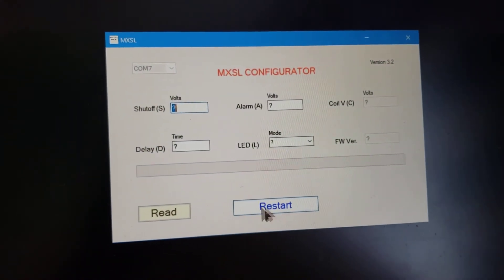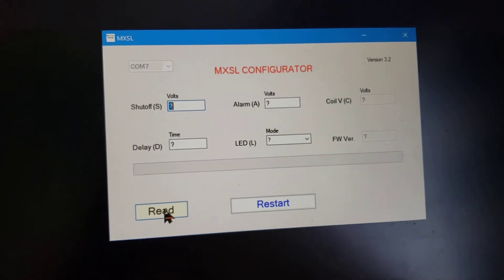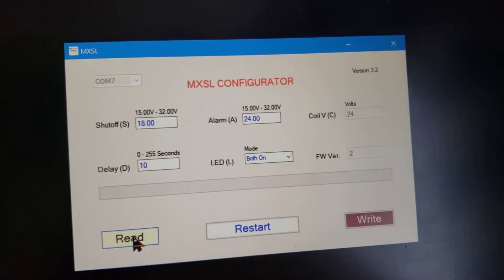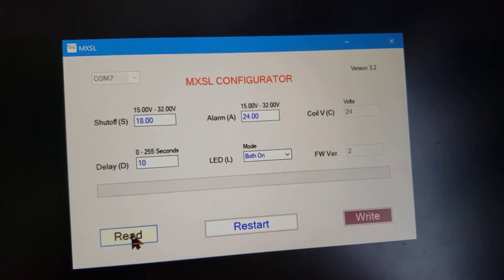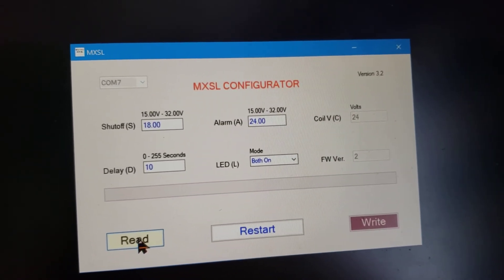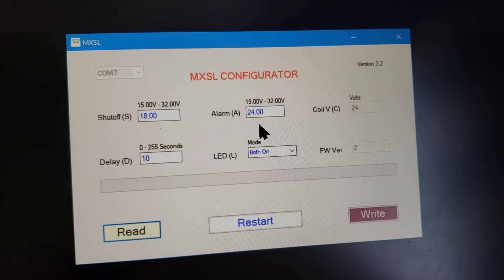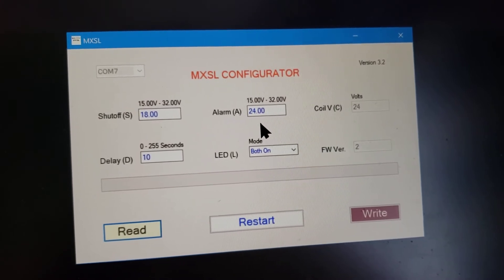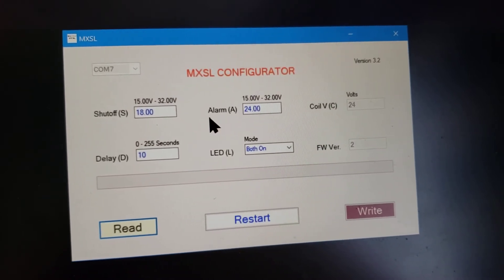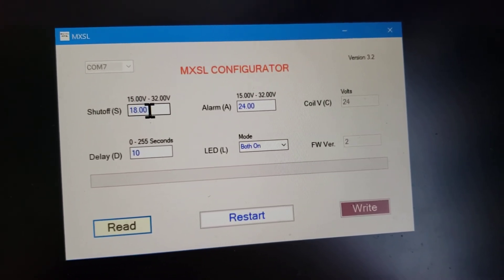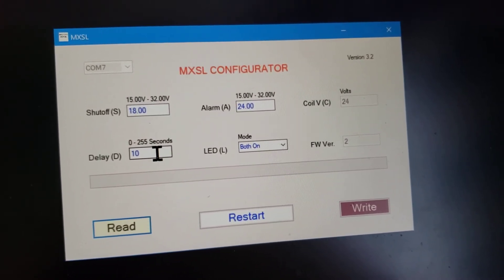So now we can click read to get the values out. So these are the values that this contactor is currently programmed to. It has a 24 volt alarm voltage. It has an 18 volt shutoff voltage and a 10 second delay.